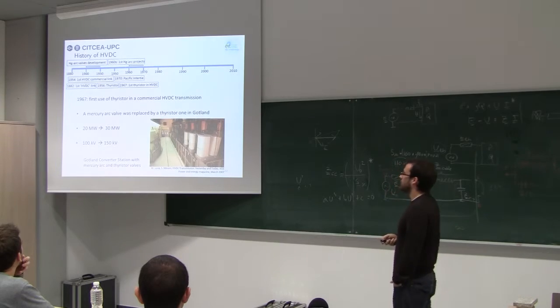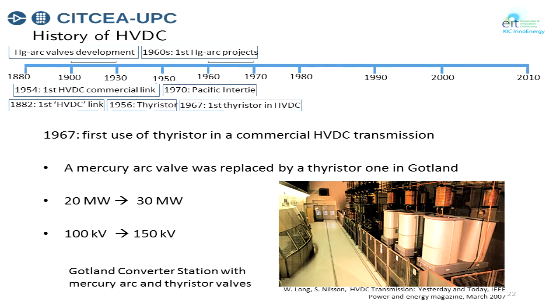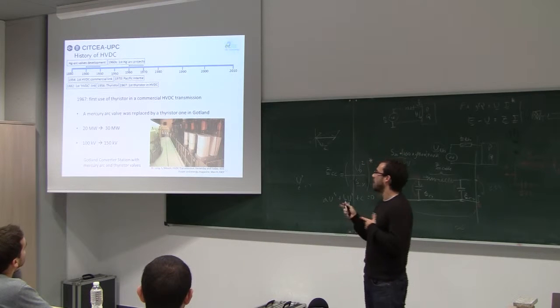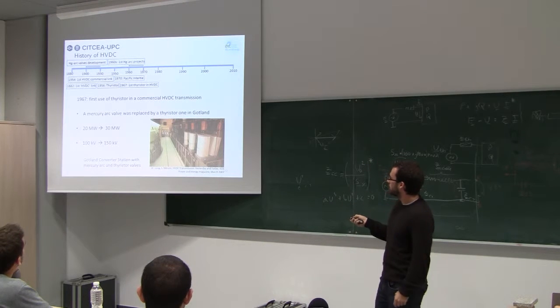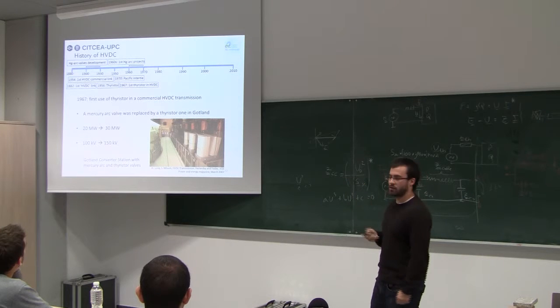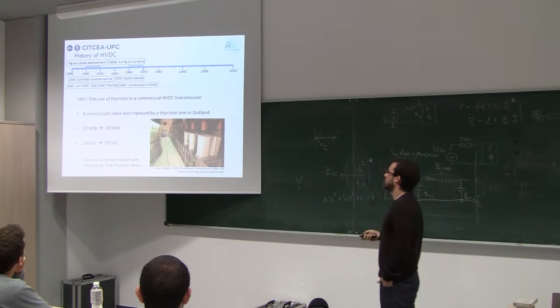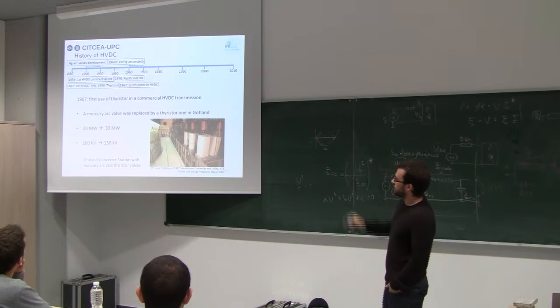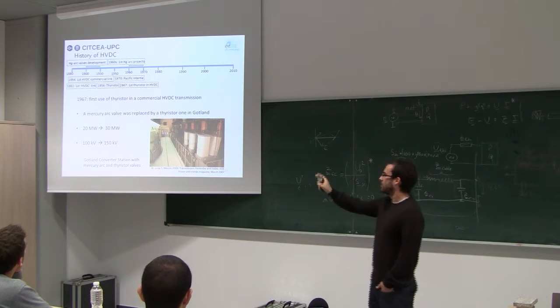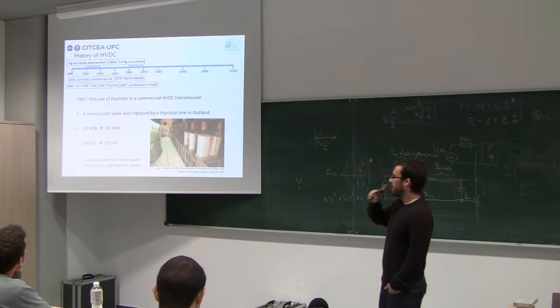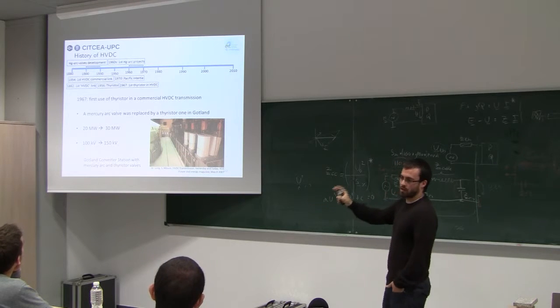Let's go to the first use of a thyristor in a commercial HVDC transmission. We see here it's in Gotland again. They replaced one of the mercury valves with a thyristor one. We see here in white the thyristor valve, and the other ones are mercury arc valves. With this installation, they could increase the power from 20 to 30 megawatts, and the voltage from 100 to 150 kilovolts.